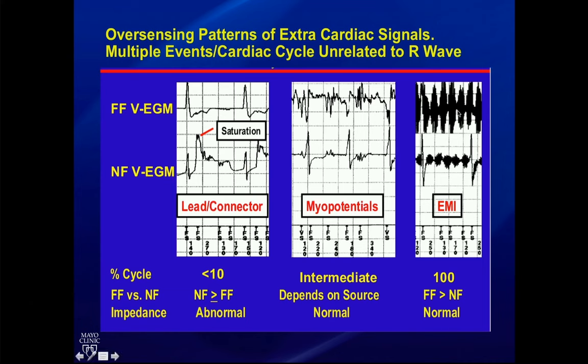Non-physiological signals don't look like VT, don't look like ventricular fibrillation. External noise, electromagnetic interference, lead fractures with the wires rubbing against each other and producing electrical noise. In those situations, we stop the device, change the leads, and figure out what the external noise is like.